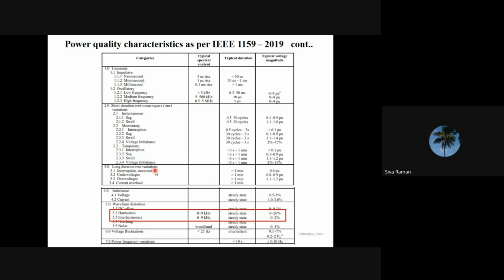Long duration voltage variation is a sustained event, an event lasting more than 1 minute, and generally this event is called long duration voltage variation. So compared to the two, in short duration voltage variation the maximum time duration is 1 minute, and in long duration voltage variation, an event which continues beyond 1 minute is generally called long duration voltage variation.